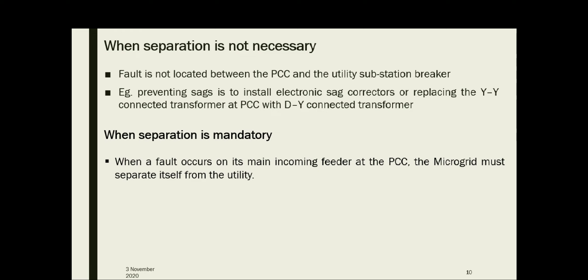These two options demonstrate how protection considerations and design options must be considered together in developing an economic microgrid. Installation of an electronic sag protector is actually costlier, but replacing a star-star interconnecting transformer with a delta-star one is a cheaper solution, even though it is less effective. When designing your microgrid, you should consider these possible solutions when separation is not necessary, and how to manage voltage unbalance.